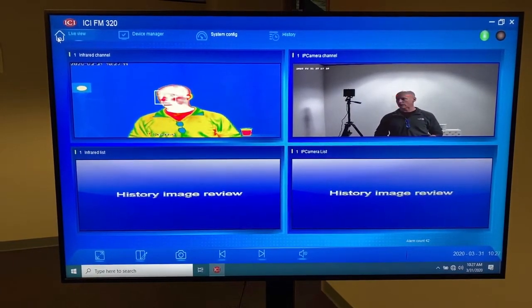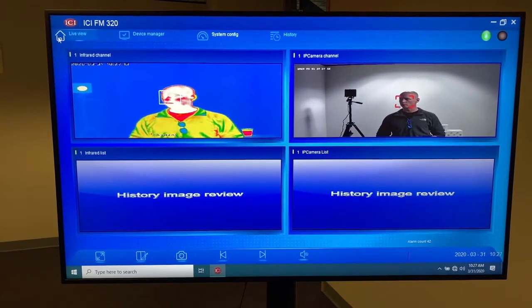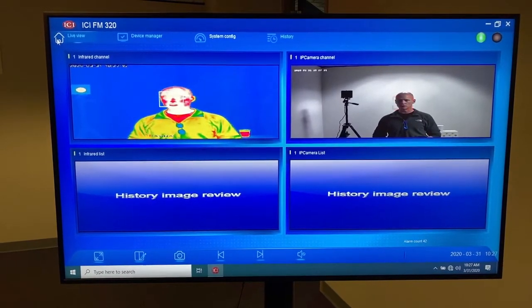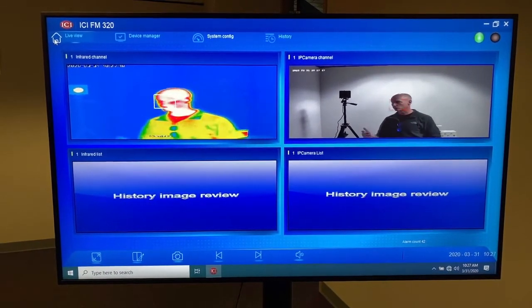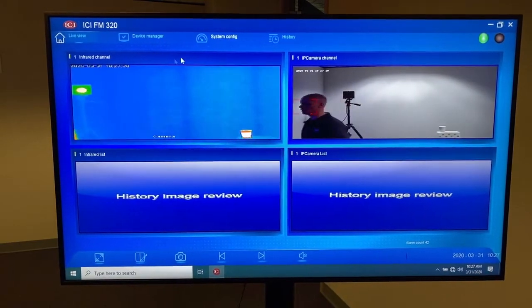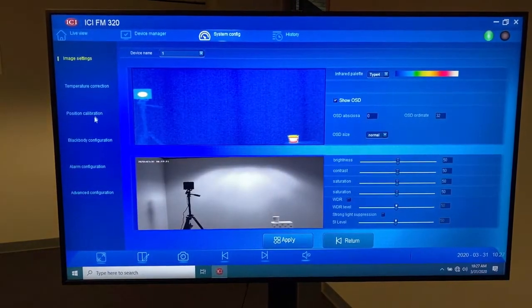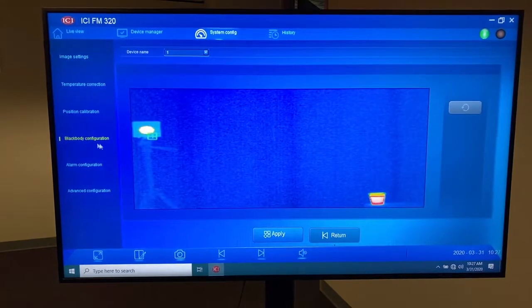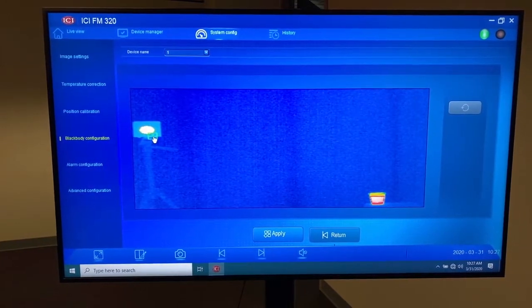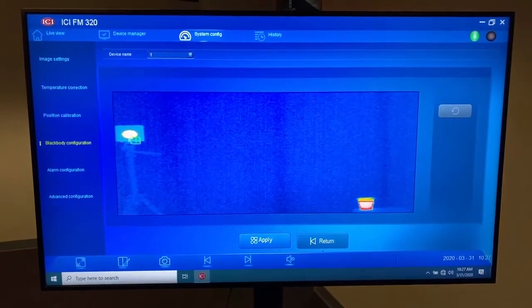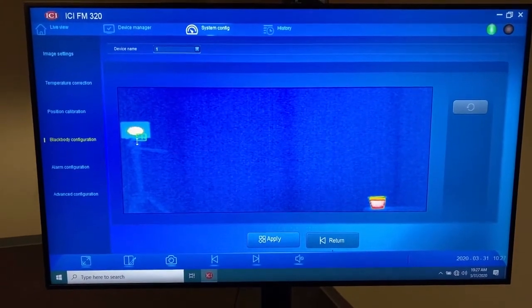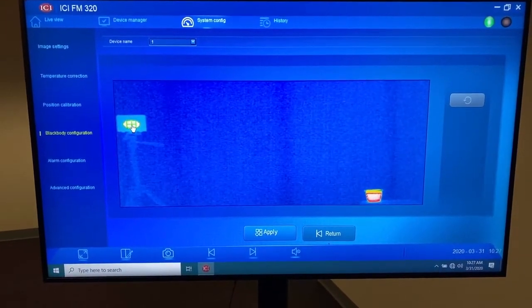nothing. So now you see that the overhead box that normally shows the individual's temperature skin reading has disappeared. First indication should be to go back and check your black body alignment. That's probably indicative of a positional error. So now the camera has no reference to actually get a temperature, so it's not going to give you anything. So realign that black body, target right smack dead center.